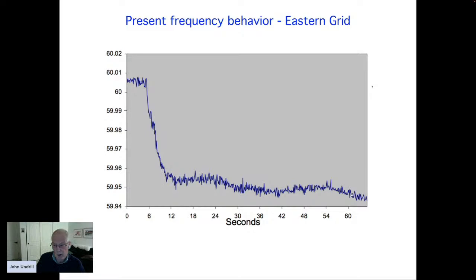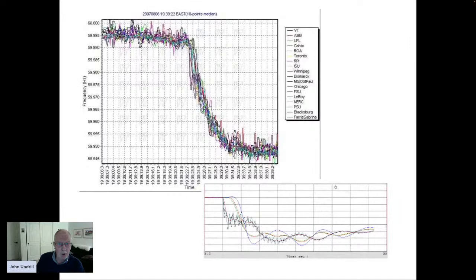But by a minute later, the fact that this frequency has gone down and has not started to recover would be starting to get people worried, because the behavior of the system must, to be successful, recover back to the 60 cycles. This is not where protection is going to operate and trip generators. It's not where under frequency load shedding is going to operate, but it's indication that things are not coming back the way they should. Here's a recording from basically all of North America recording system run by one of the universities in the east of the USA.